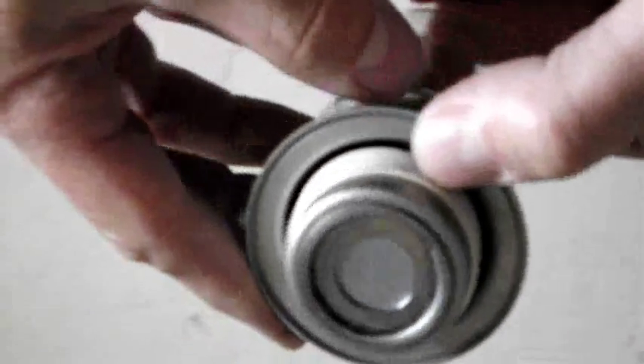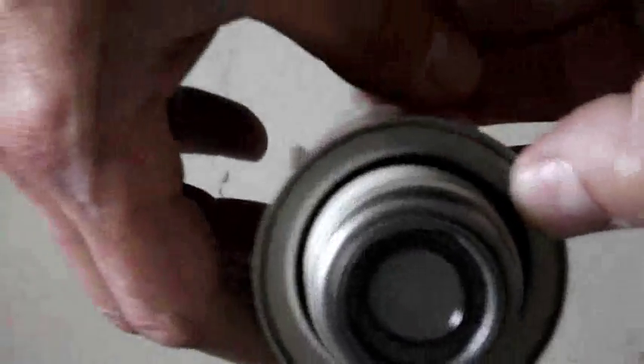No signs of where it's actually let in air other than there's a very very small dent in the beryllium window just here. It doesn't look bad but it may be just enough to have let air in. There's certainly no cracks on the glass.